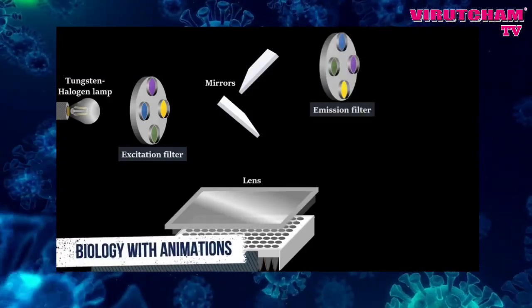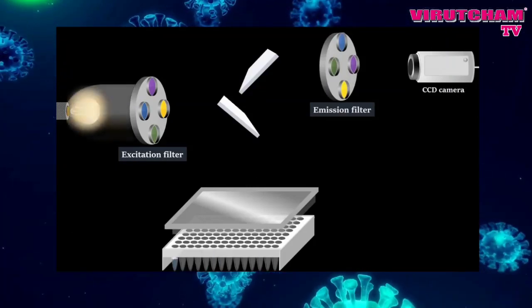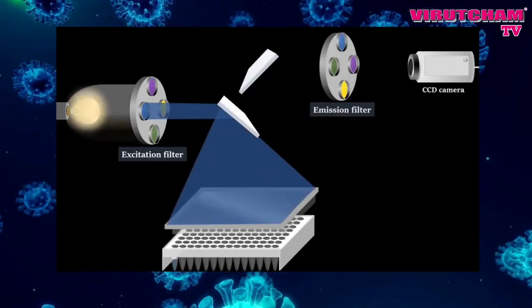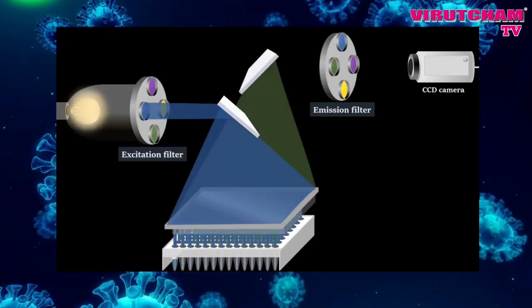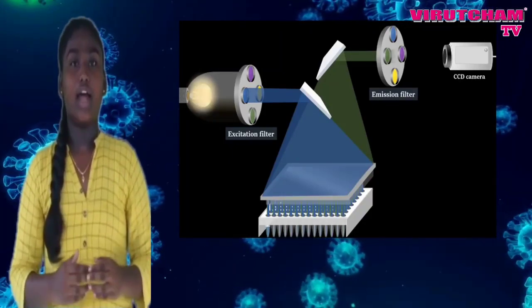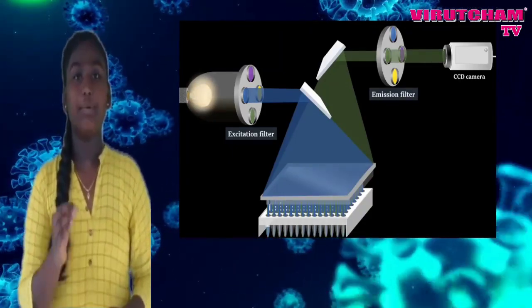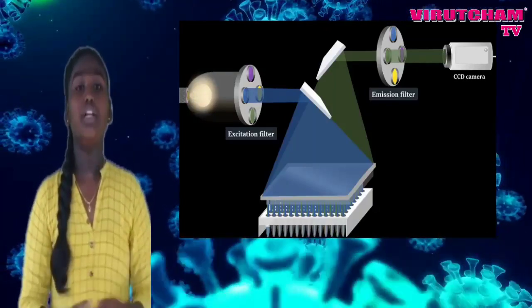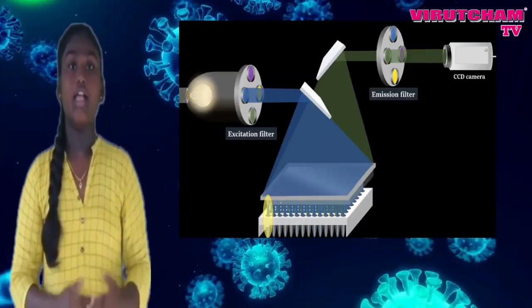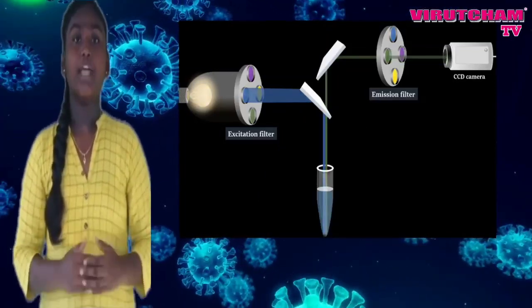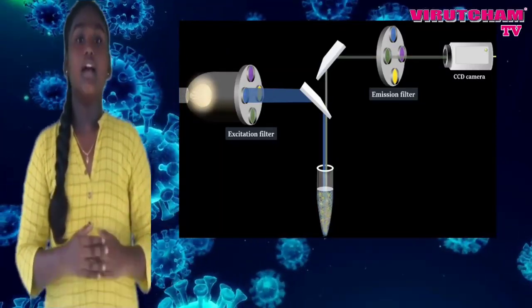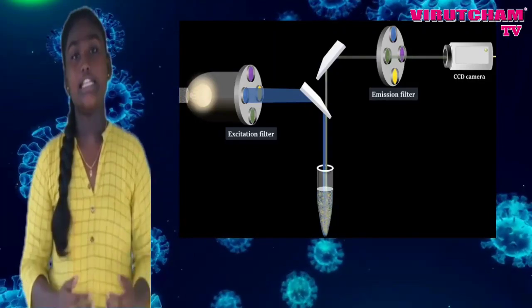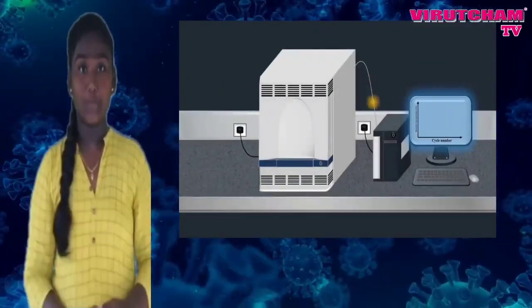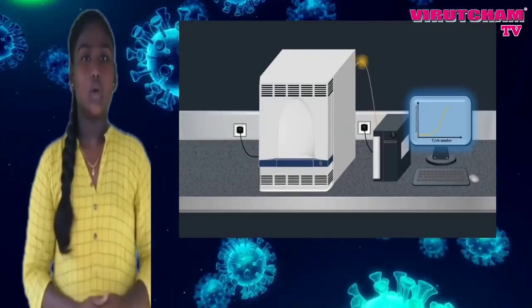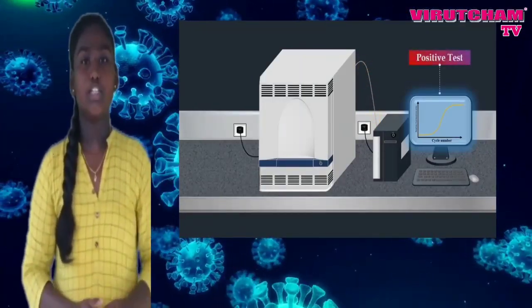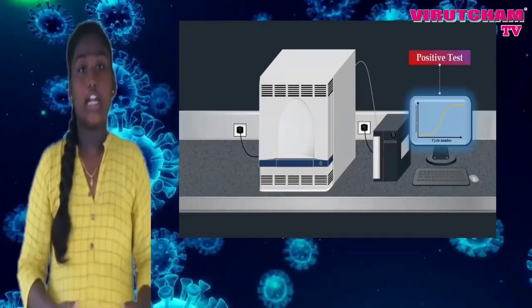Filtered light from the lamp is reflected off the mirror, passes through a condensing lens and is focused at the center of each well. Then the fluorescence emitted is reflected off the mirror. A charge-coupled device CCD camera is used. In each cycle of PCR, light from fluorescence can be detected by the CCD camera, which converts the light captured into digital data. This is known as real-time PCR, which monitors the process of the PCR in real time.